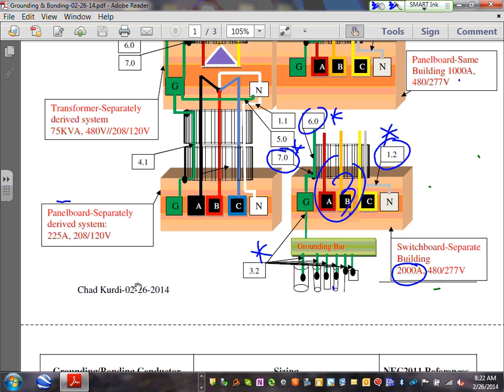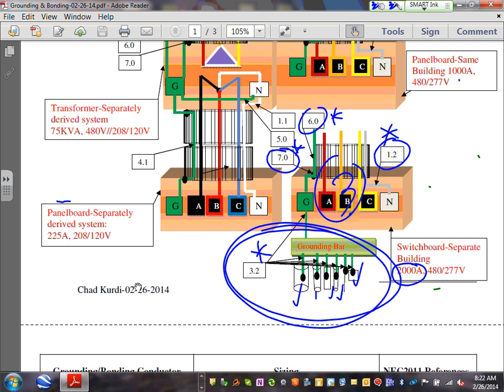So what they want you to do, Karen, when you go to the second building, is establish a grounding electrode system. Meaning the second building is going to have water, so you have to bond to the water. Can you guys see that? You need to bond to the water. You could also have a plate, a ring, concrete-encased electrodes, ground rods. So you do the grounding electrode system exactly like you do at the service. Can I get you guys to understand? So you have to create a grounding electrode system.